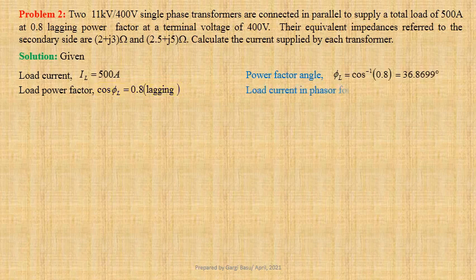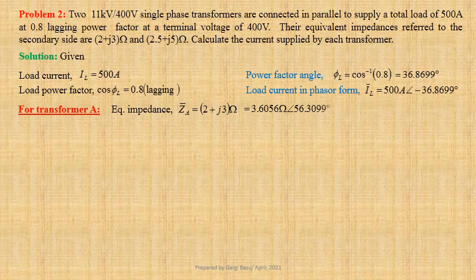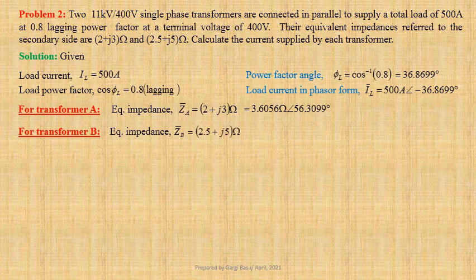Power factor angle phi L equals cos inverse 0.8, that is equal to 36.8699 degree. Load current in phasor form IL equals 500 ampere at an angle minus 36.8699 degree. For transformer A, given equivalent impedance ZA equals 2 plus J3 ohm. This may be written in polar form as 3.6056 ohm at an angle 56.3099 degree. For transformer B, given equivalent impedance ZB equals 2.5 plus J5 ohm. Let us now determine ZA plus ZB.